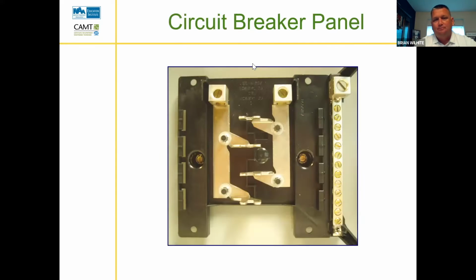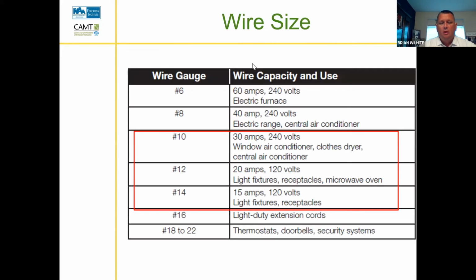You know, if we look back on our chart here, it says 12 gauge, 20 amps is our max for 12 gauge. Well, if I didn't have that breaker on there and I decided to run 60 amps through that 12 gauge wire, what's going to happen to that wire? Melt. It's going to start on fire. Yeah, it's going to start on fire. And so that breaker is limiting the amount of amps I can have go through that wire and protecting that wire from starting on fire.